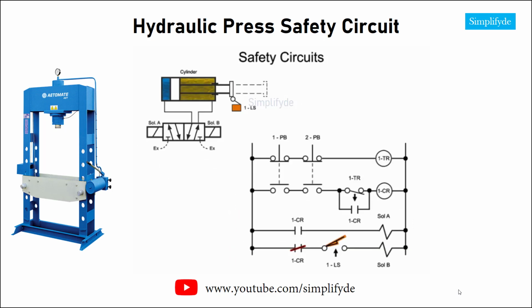Another way to prevent tie-down is to utilize a double solenoid two-position valve. The valve is much simpler and less expensive, but requires a more complex circuit utilizing an off-delay timing relay, a normally open timed-open timer contact, a control relay, two solenoids, and a normally closed limit switch. When both push buttons are in the unactuated position, the timing relay is energized and the normally open timed-open timer contact is shut. No power can flow to the control relay.